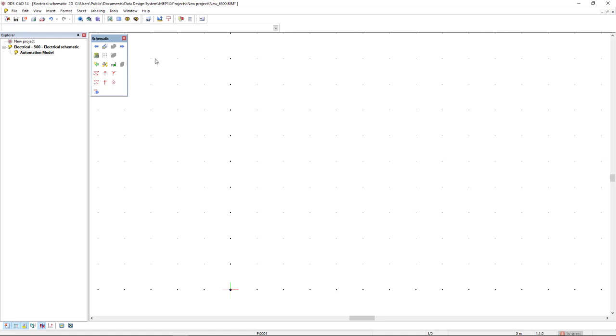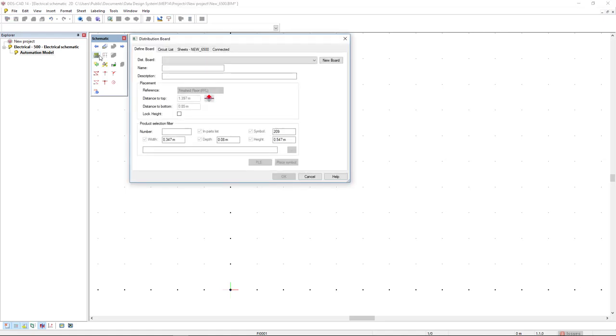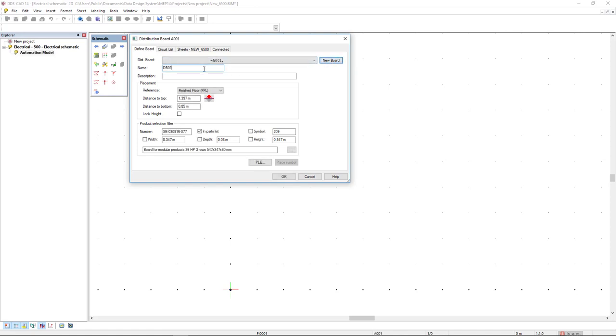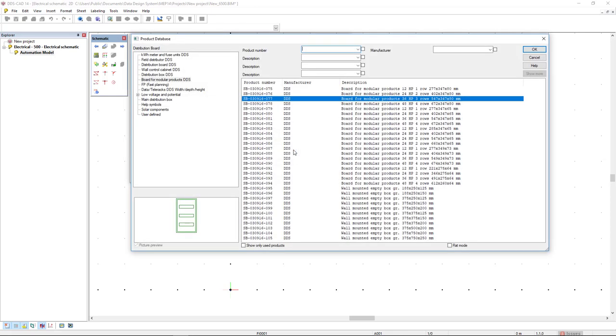I will start on the electrical schematic. In the schematic toolbox we find the distribution board function. First, we're going to define a new board, so we click on the new board button. I will type DB01, and we can open the product database of boards using the three dots button.